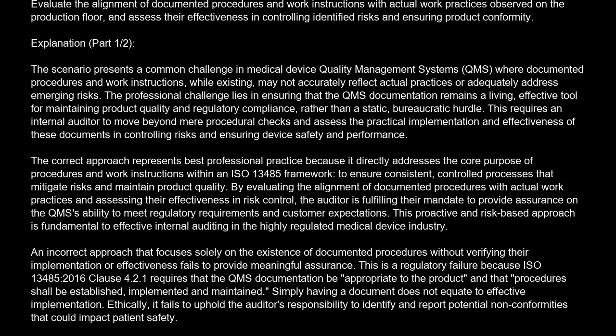The correct approach represents best professional practice, because it directly addresses the core purpose of procedures and work instructions within an ISO 13485 framework, to ensure consistent, controlled processes that mitigate risks and maintain product quality. By evaluating the alignment of documented procedures with actual work practices and assessing their effectiveness in risk control, the auditor is fulfilling their mandate to provide assurance on the QMS's ability to meet regulatory requirements and customer expectations. This proactive and risk-based approach is fundamental to effective internal auditing in the highly regulated medical device industry.